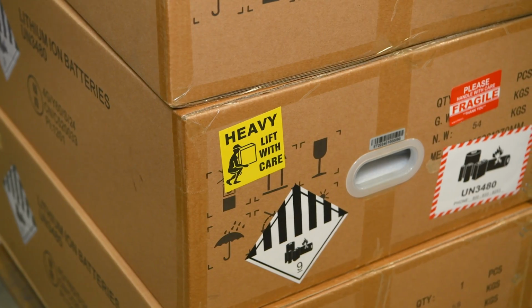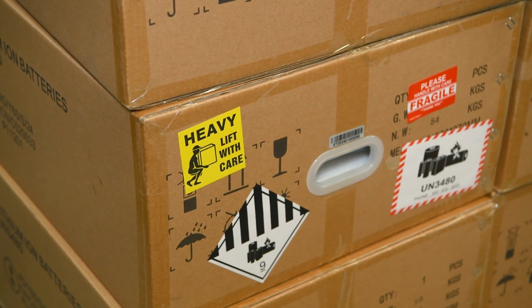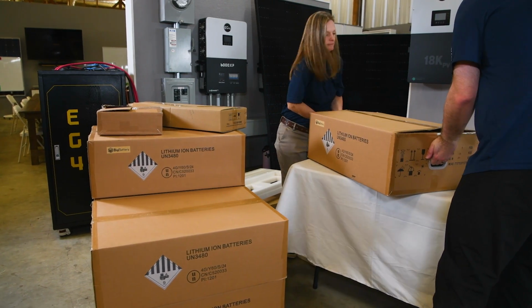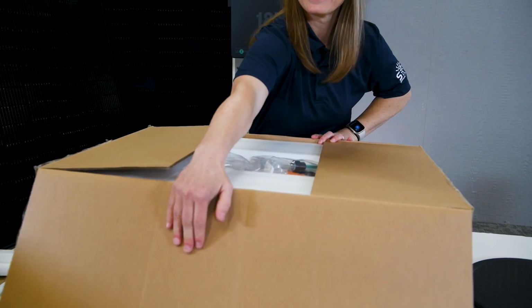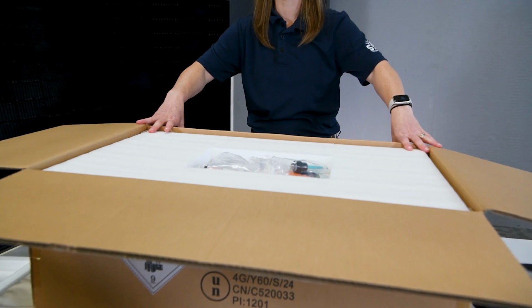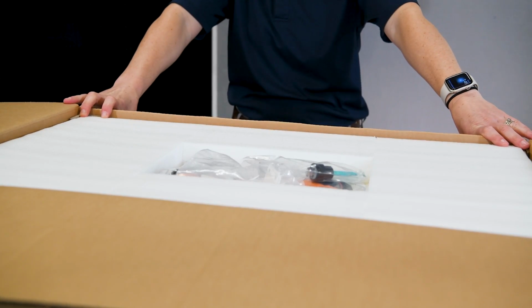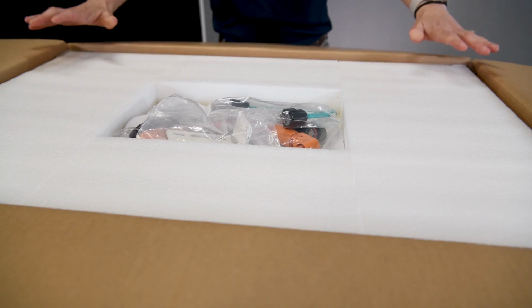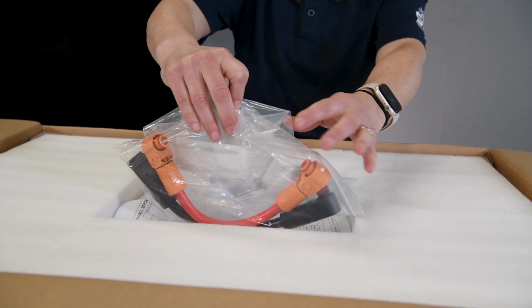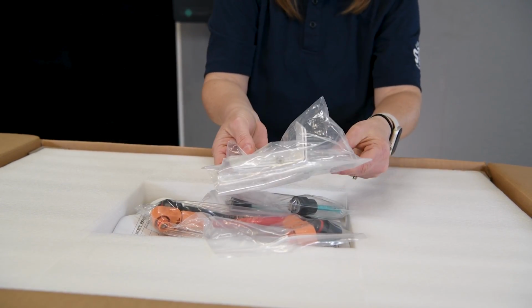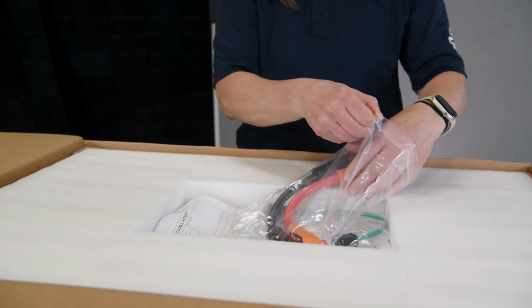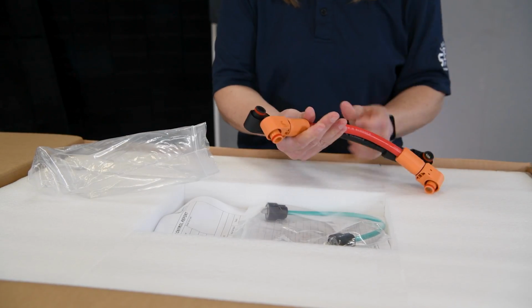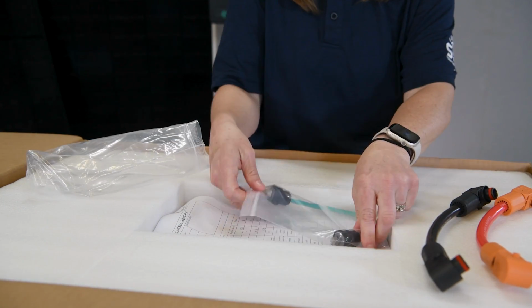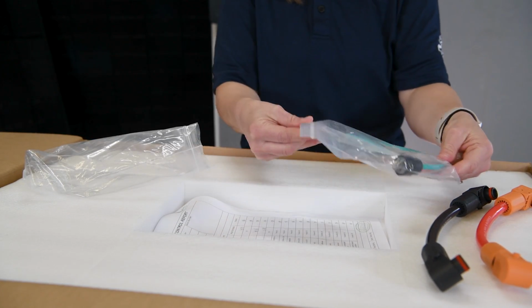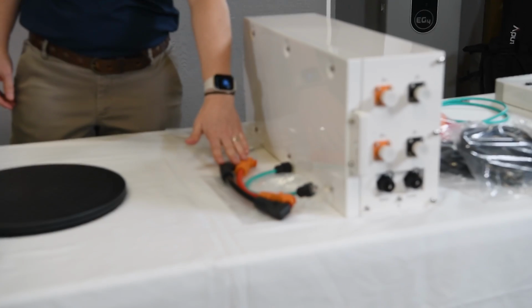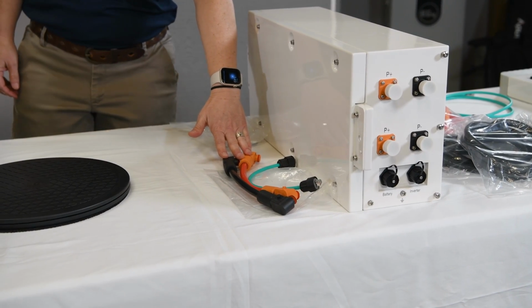It's the heavy one. These batteries weigh about 114 pounds, so be prepared to have a friend on hand to help out if needed. When you open the box, the first thing you'll notice is the thick foam padding that's there to keep everything well protected during shipping, making sure it all gets to you in one piece. In the center, you'll find a bag with stainless steel screws, drywall anchors, and L brackets for mounting your battery securely to the wall. There's also two 12-inch battery-to-battery parallel cables with quick connect Amphenol connectors on both ends, along with an 8-inch communication cable.